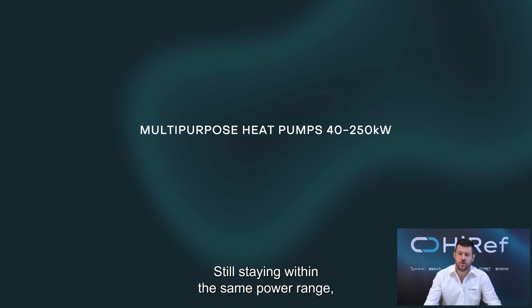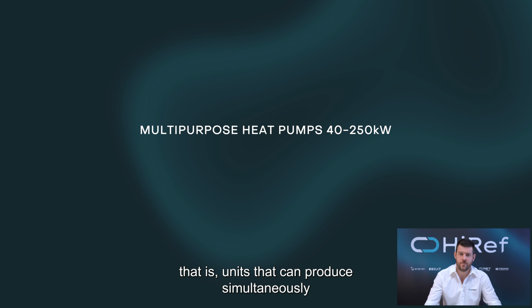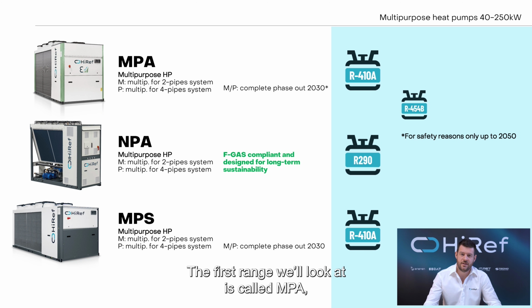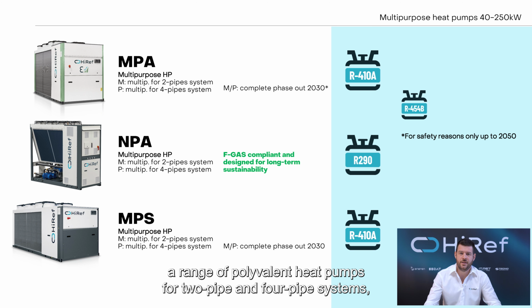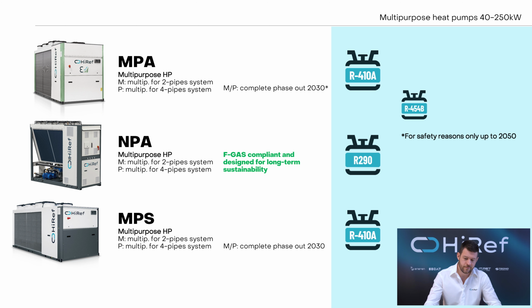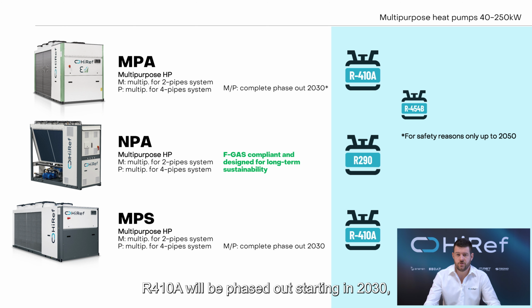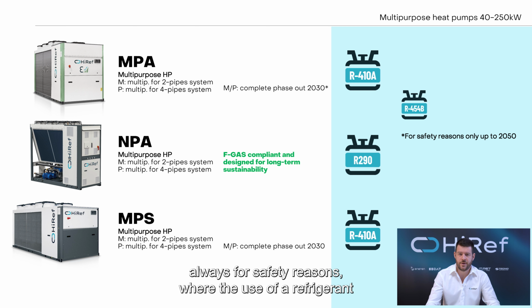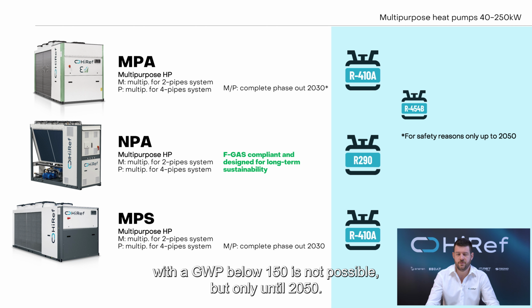Still staying within the same power range, let's now take a look at the polyvalent units. That is, units that can produce simultaneously chilled water and hot water. The first range we'll look at is called MPA, a range of polyvalent heat pumps for 2-pipe and 4-pipe system, for which 410A will be phased out starting in 2030. While 454B will be an alternative, always for safety reasons, where the use of a refrigerant with a GWP below 150 is not possible, but only until 2050.